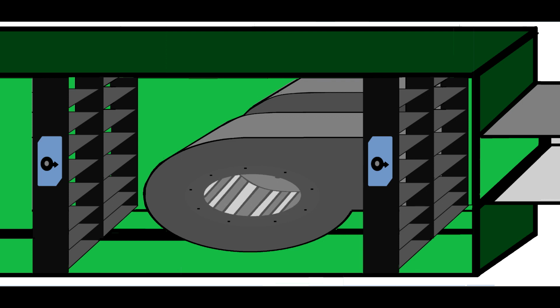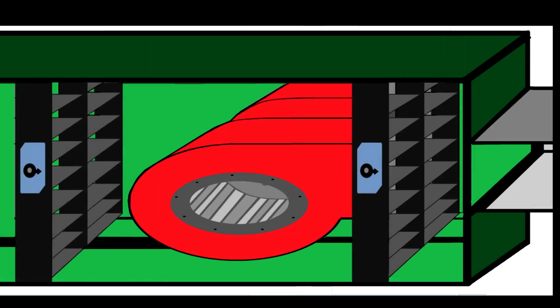Again, you can run the twins, and you can choose. Each fan would have the capability to run the system on its own. If one crashes, the other one will take over. You have dampers to segregate the faulty fan, so you won't have an air closed loop, so you won't lose the air capacity.